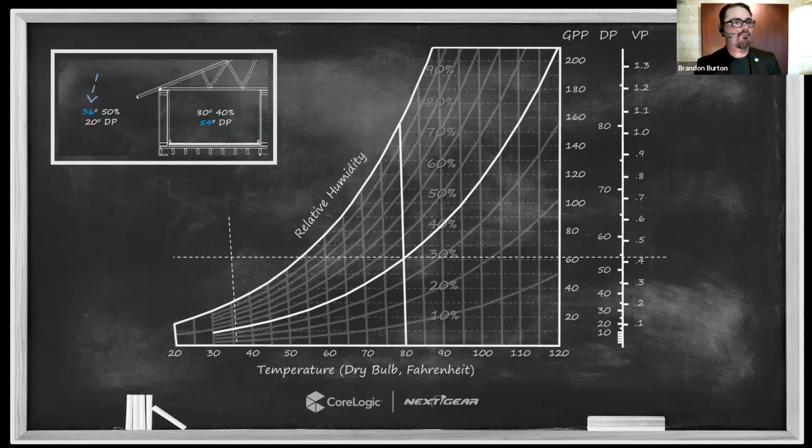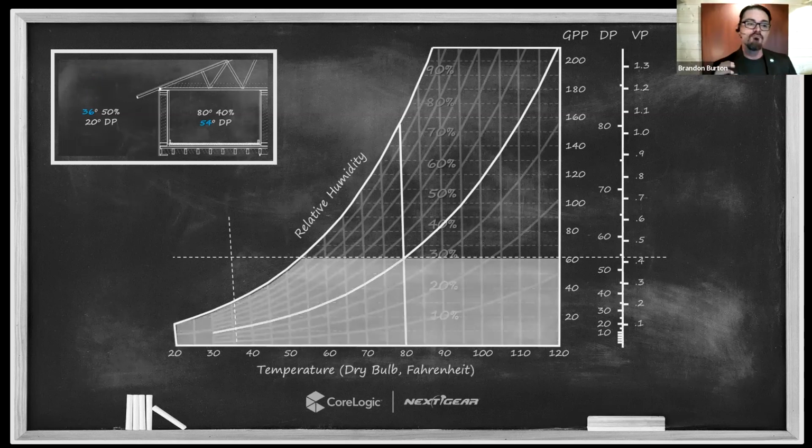That's the first indication that we've got a problem. So any of this air in the building that moves inside of that wall cavity and cools down close to the outdoor air temperature, all of a sudden it's going to have more moisture in it than the air can support. And guess what's going to happen to that moisture? That moisture is going to condense. It's going to sweat out onto those surfaces. Those surfaces are going to become wet. They're not going to get drier. They're going to become wetter. So the amount of moisture we have in the air inside the building is too great for the surfaces that are going to be anywhere near that outdoor temperature. In fact, any surface that's below the dew point, which is 54 degrees Fahrenheit. Okay, so that's dew point. That's how dew point can really assist in the process. That problem is going to exist throughout that entire exterior wall assembly.